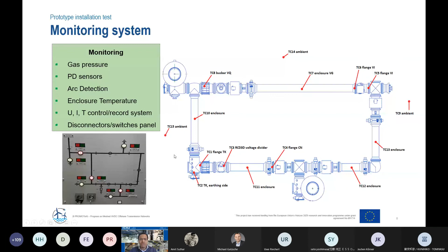And then, as I mentioned, inside of the GIS there are gas pressure measurements, partial discharge monitoring, and also arc detection. And here you see we check the switch panel, the position of the disconnector and earthing switch, so that can also be controlled. So everything is recorded in our system.